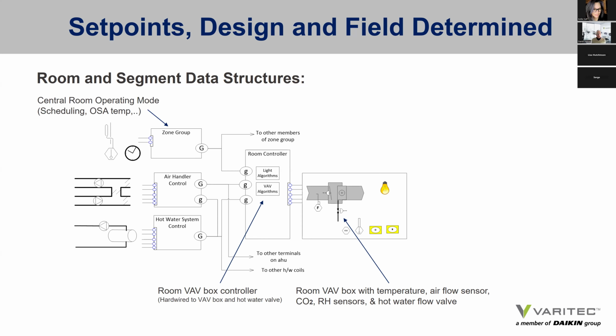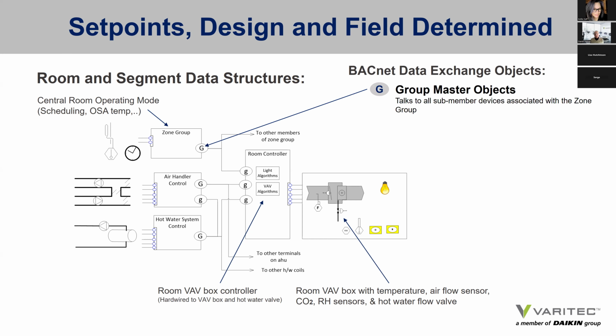Then there's the central room operating mode and zone group. There's the air handler controller, and all of these devices are wired and connected and exchanging data between each other. And the mode of exchange or the language of exchange is BACnet protocol frequently. There are other protocols like LON and Modbus, but what we see mostly today in our market is BACnet.